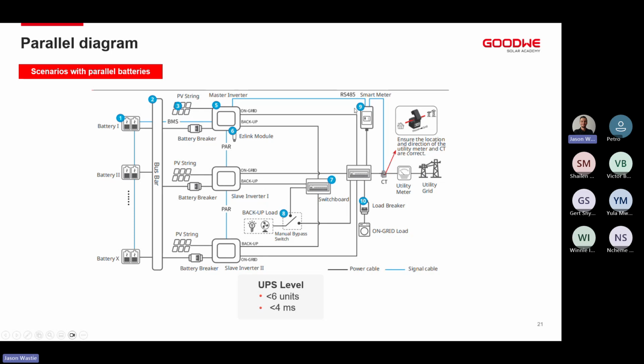You'll see there is a smart meter that needs to be installed as well. We have external smart meters that can be installed. The only time we need to install an external smart meter is when the inverter is installed more than 10 meters away from where we are going to clamp on the CT. Included in the box with the inverter is a 10-meter long RS485 cable with CT connected. Anytime we need to extend past that, we will connect an external smart meter.